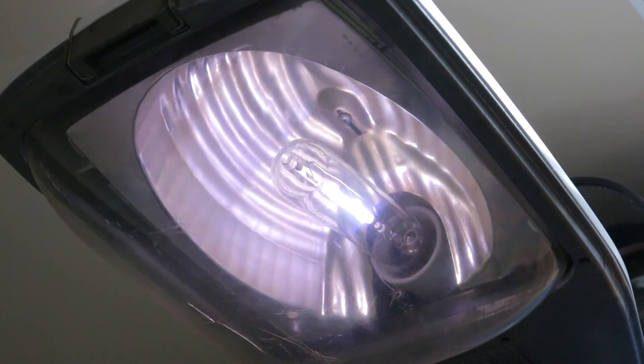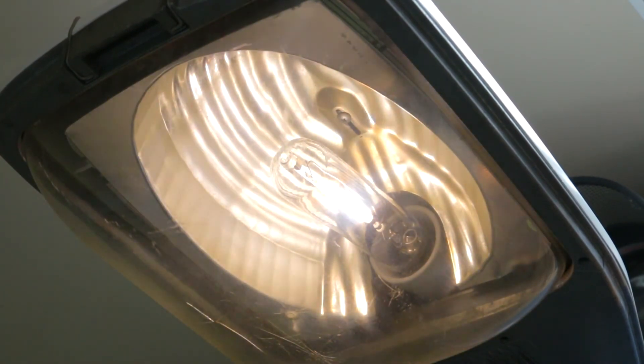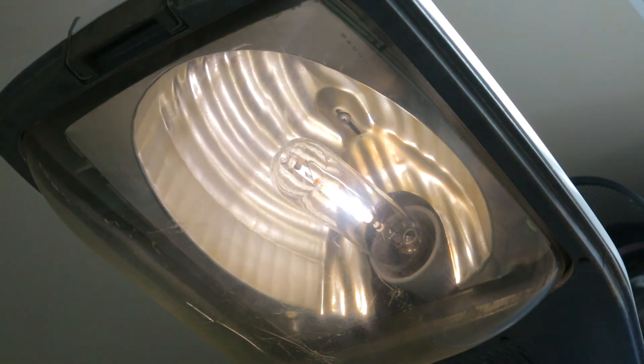You'll notice it starts white. That's because these GE Lucalox lamps have a very high xenon pressure in the gas fill. Once the sodium starts to vaporize, that's when you start to get the characteristic golden yellow from the high-pressure sodium.